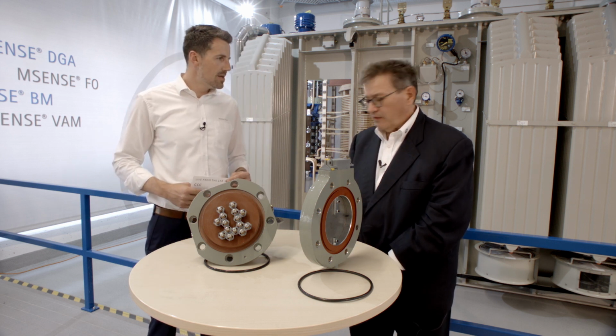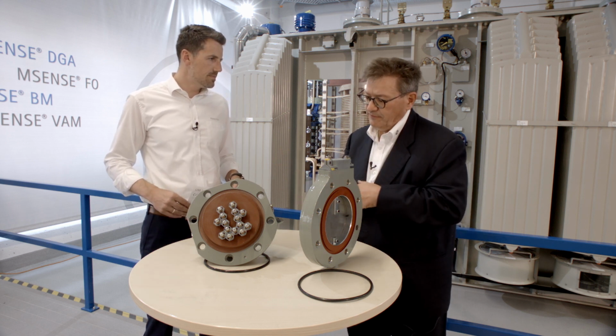Tullio, maybe you can please explain to our participants why terminal boxes should be used for transformers. Thank you, Stefan. Here we have what we call two typical devices or components that we name components for tank. Tank components. Yes, because the characteristic is that these parts have to be installed in the tank or on the tank, depending where. Here we have, as you said, a terminal box. Terminal box is useful to bring out the voltage signal coming from the current transformers, which are installed below the bushings in the oil compartment. The transformer maker needs to bring out the signal from the current transformers to the cabinet, to the outside cabinet, to the devices which are downstream of the transformer.